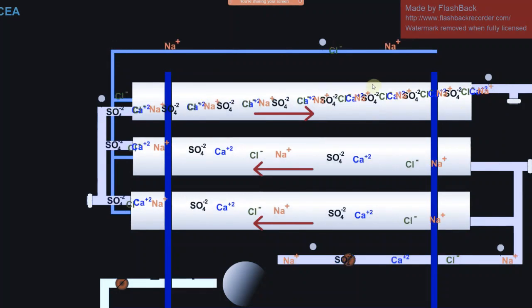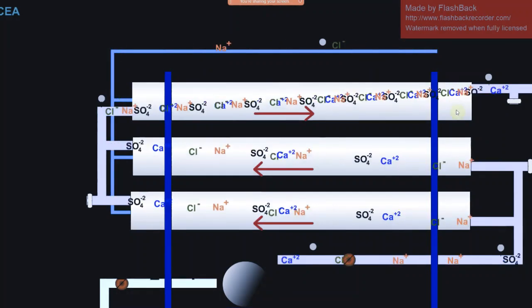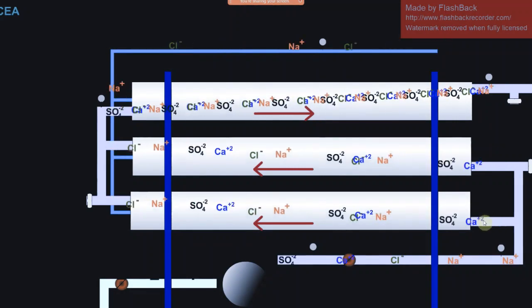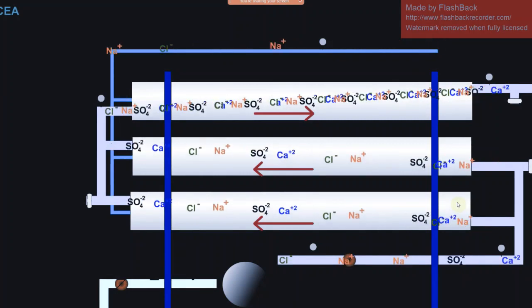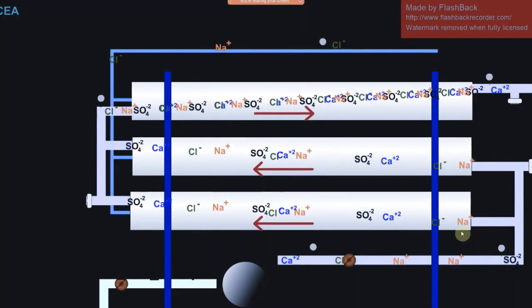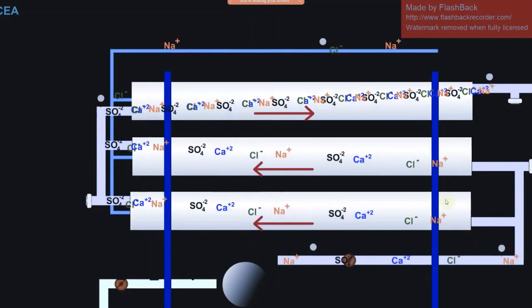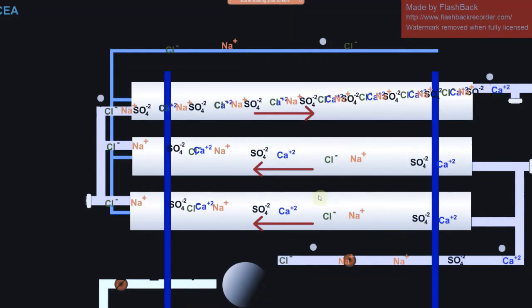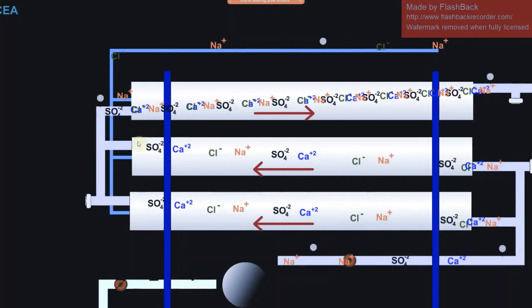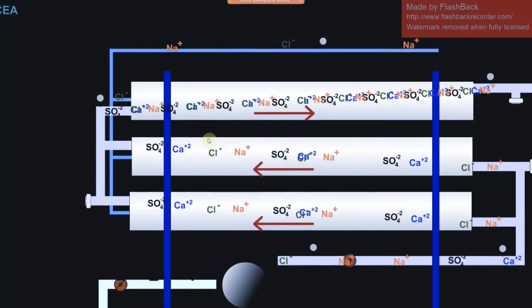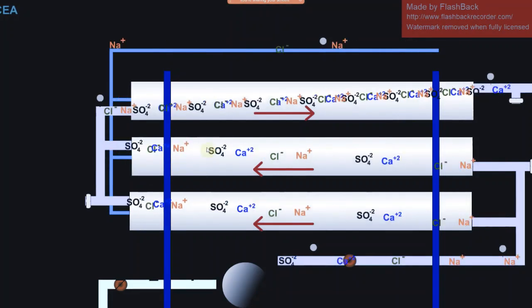So if you are not finding high DP in the second stage, but you are finding high DP in the first stage itself, then it may be colloidal fouling, organic fouling, or suspended solids fouling, which are happening in the front end membranes, in the lead membranes. But if scaling has to happen, it will happen first in the tail end membranes of the second stage, or if it is a single stage only, it will happen in the tail end membranes of the first stage itself.